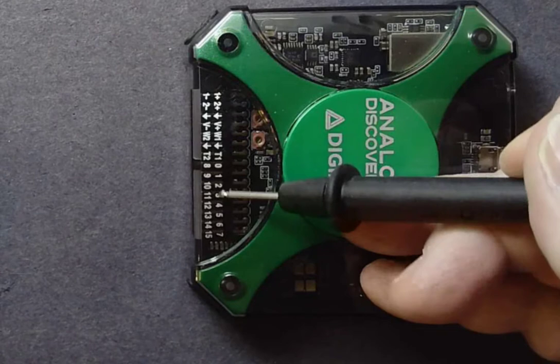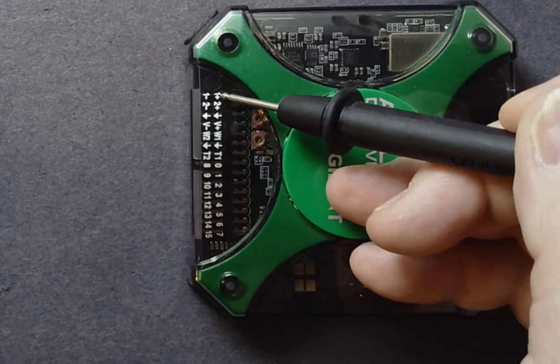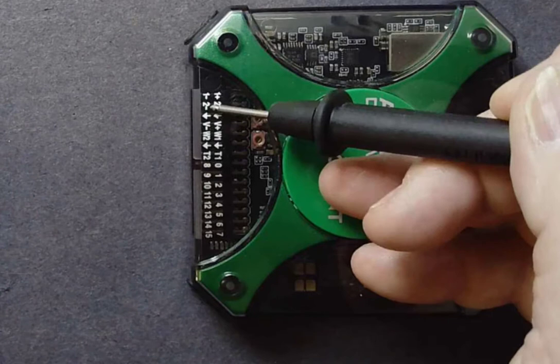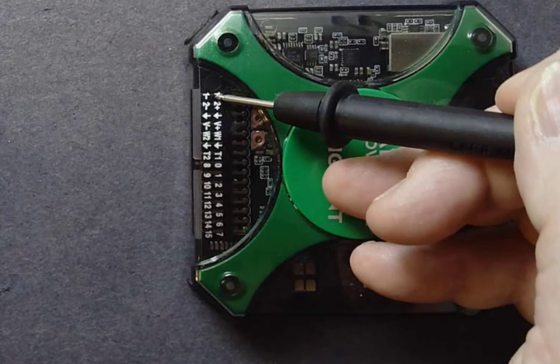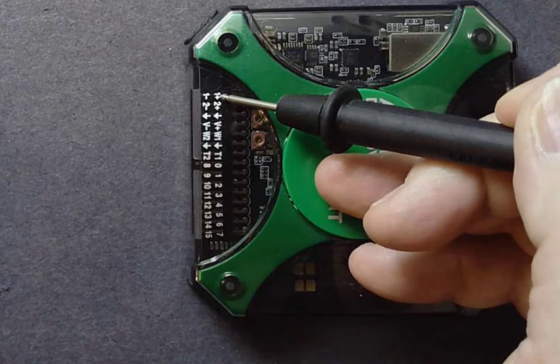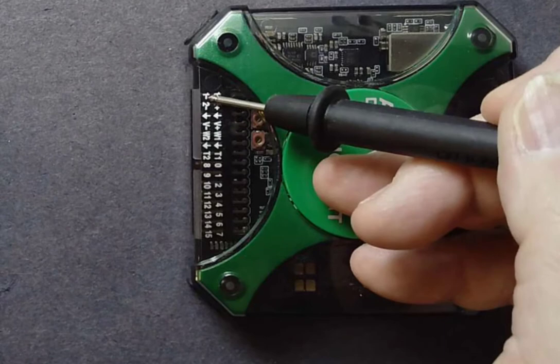We're always going to be measuring the voltage difference between the plus and minus of each channel. If we're looking at a signal that's single-ended, referenced to ground, then we're going to want to connect the minus input to ground. If we just let the minus input float, not connect it anywhere, we're going to get noise. We're not going to be seeing the voltage difference between that input and ground. Always keep in mind, if you're looking at a single-ended signal, you're going to want to connect the minus input to ground.